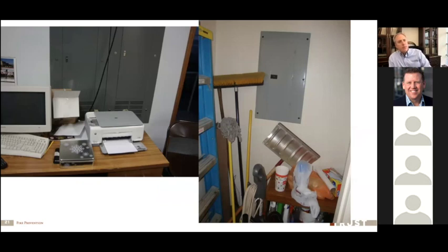But here's an example of some electrical panels. You could maybe get these doors open in a pinch, but the objects placed in front of the panels could make access to those panels in an emergency difficult. And if we've got combustible materials here, remember, this is also a potential ignition source. So we need to keep things 36 inches away from these electrical panels, that 36-inch space in front of these panels up to 72 inches high.